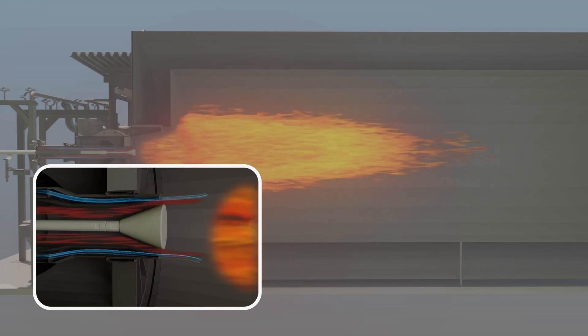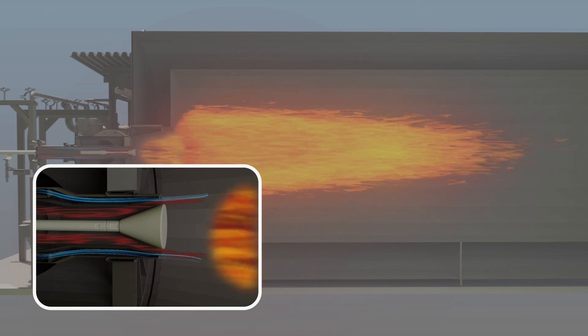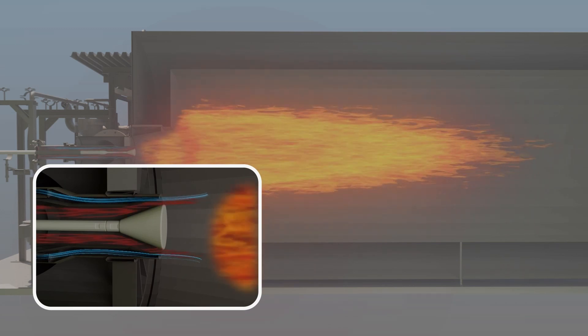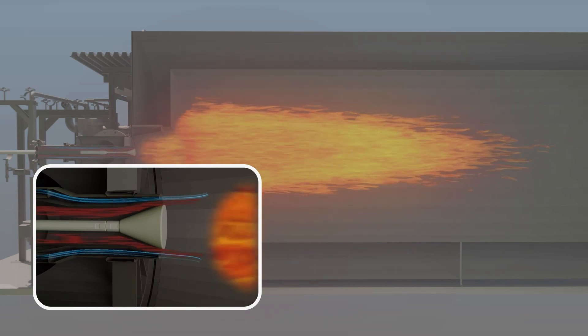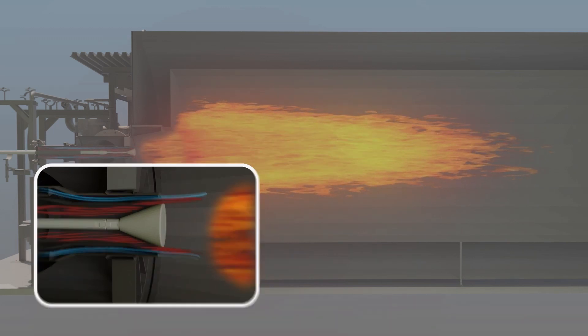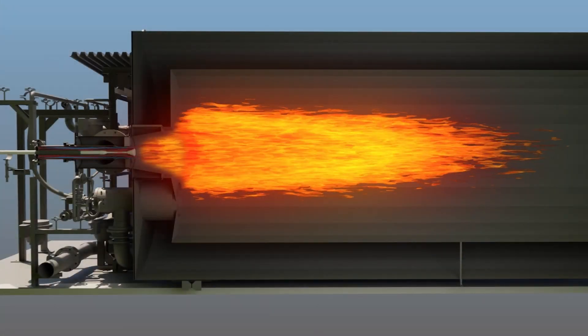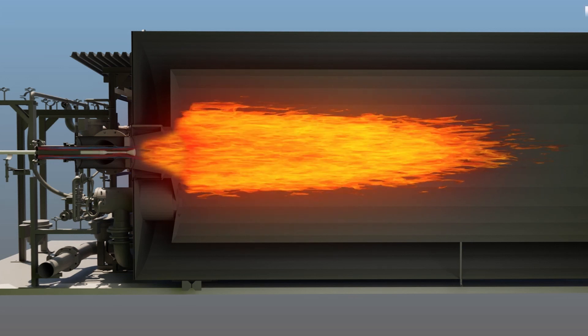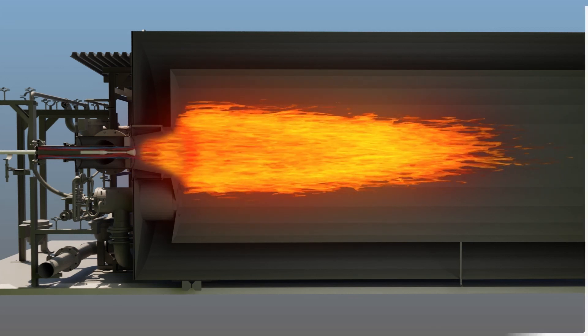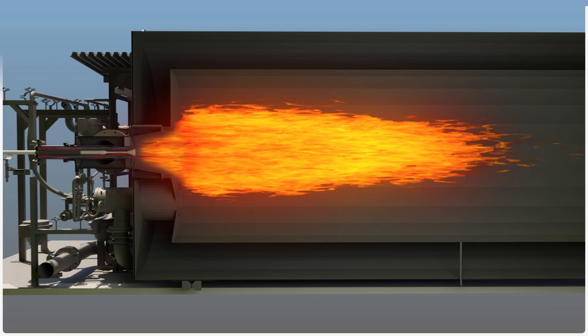As the position is controlled via differential pressure, this is done instantly and guarantees a constant outflow velocity, giving the name Constant Speed Burner or CSB. With this technology, the safe outflow velocity is always ensured without the need of additional nitrogen or other dilution gases.